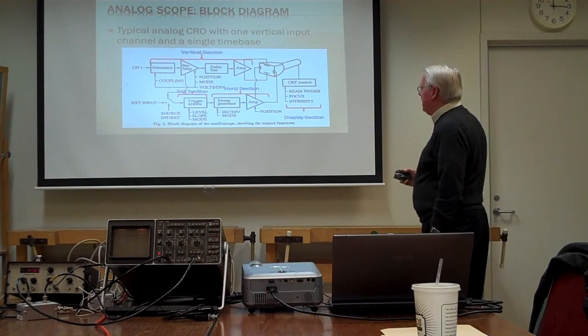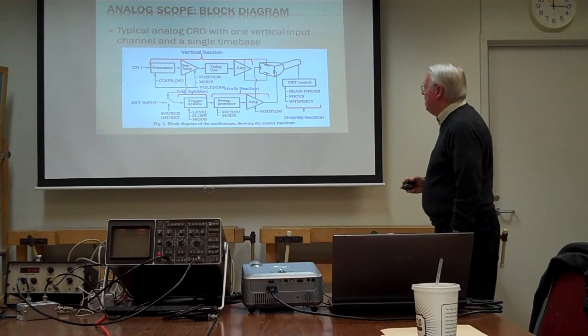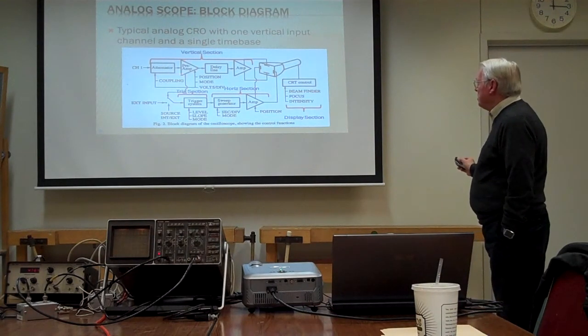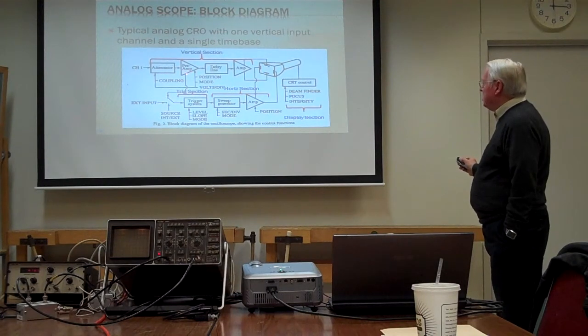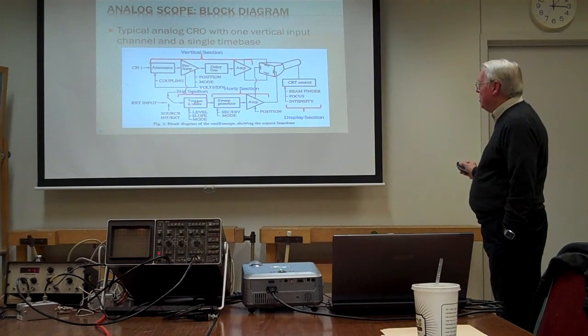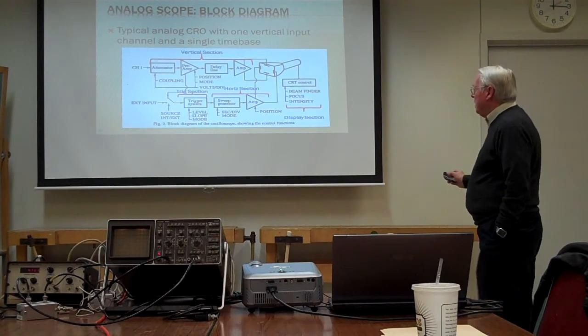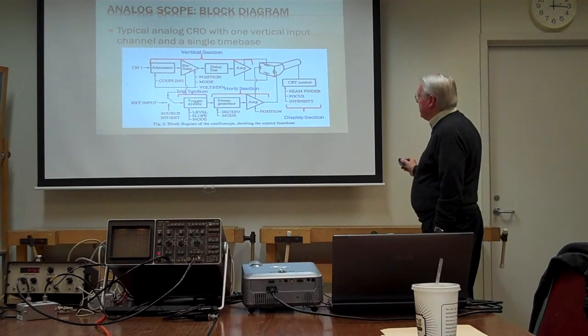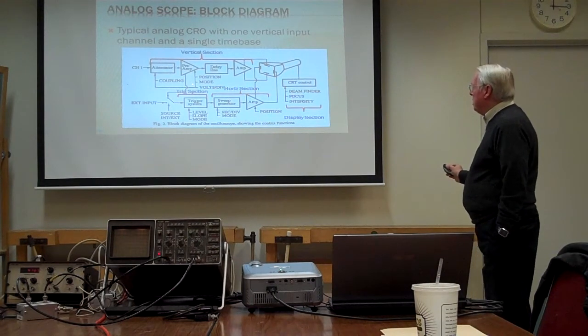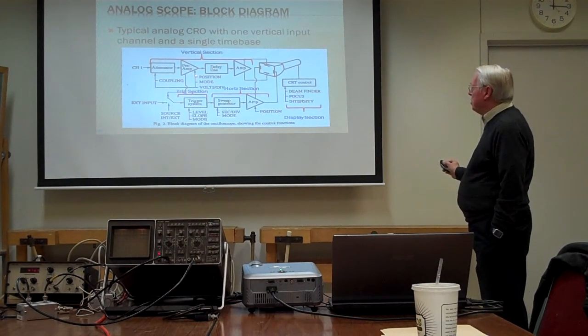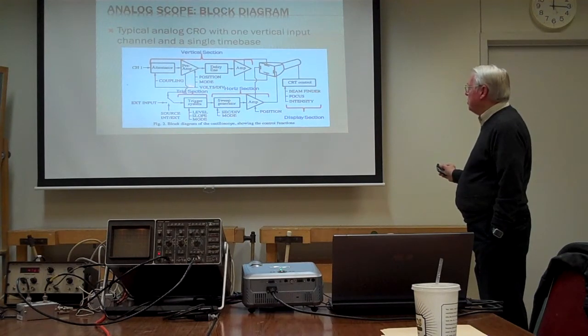We'll talk about coupling on the next slide, whether it's AC, DC, or ground. The signal is fed into a pre-amplifier section to get a little more gain, then tapped off to go into the trigger system, where at some point on the signal we pick off to start triggering. In the trigger system, we can set the level, the slope, and the mode of triggering. Also in the preamp, we can control the vertical position on the screen, the mode of operation, and the volts per division.